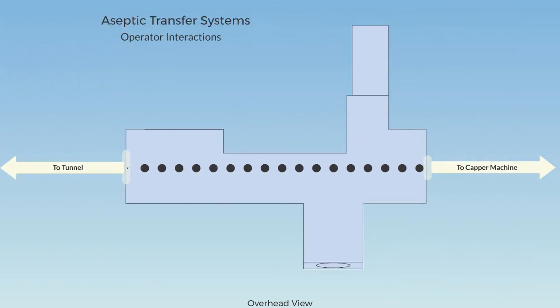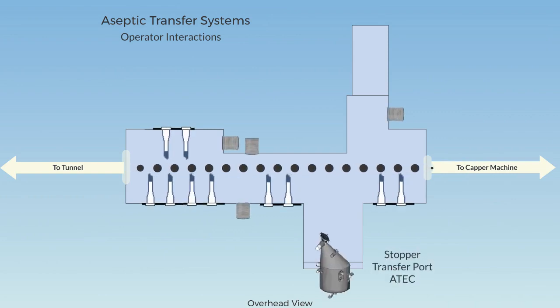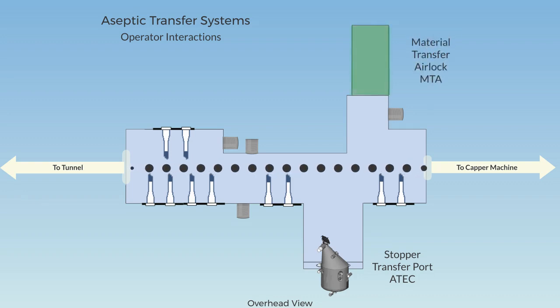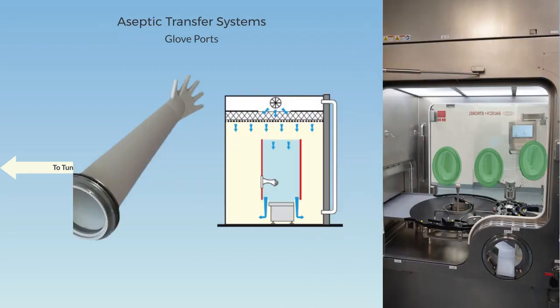Operators interact with the isolator using glove ports, rapid transfer ports, better known as RTPs, and the material transfer airlock, a transfer chamber connected to the isolator that allows materials to be transferred in or out of the isolator and maintain an aseptic environment. Glove ports create a physical barrier between the operator and the working chamber and allow the operator to perform manual work inside the isolator and maintain the Grade A environment.